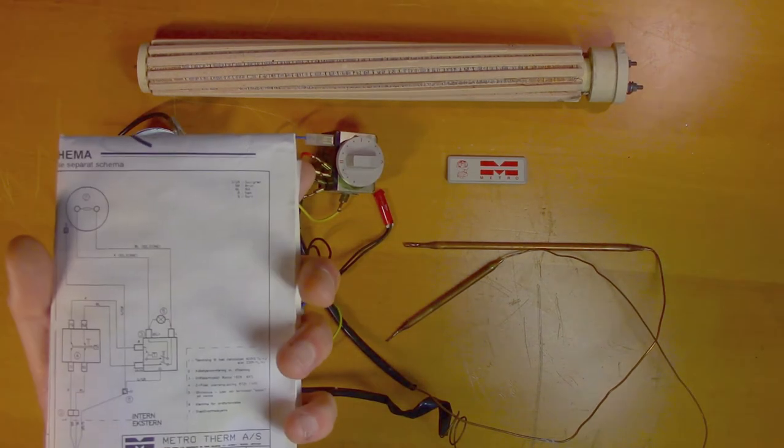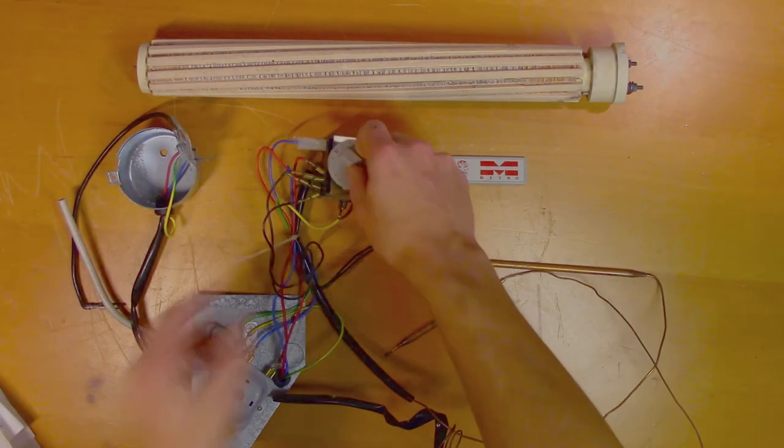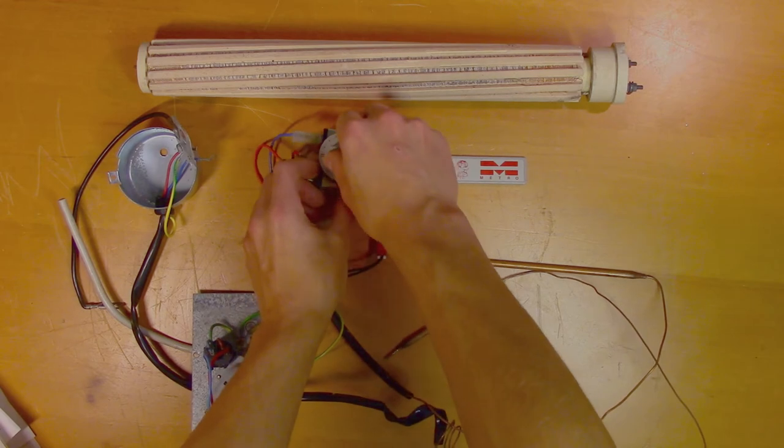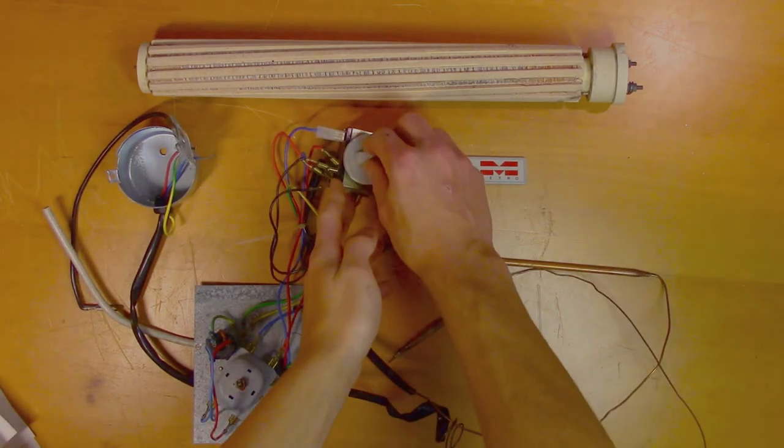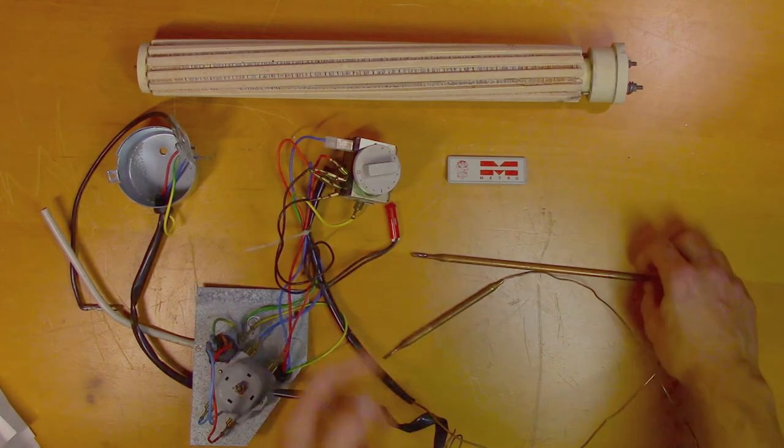And then we continue to the thermostat relay. And that's this thing right here. So here you decide how hot you want your water. And this determines at which water temperature the relay will trip. And it measures the water temperature with this long copper rod.